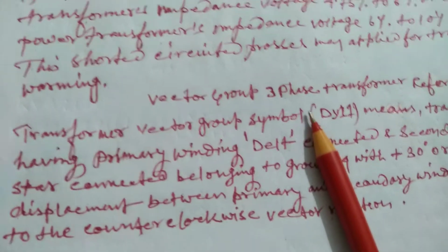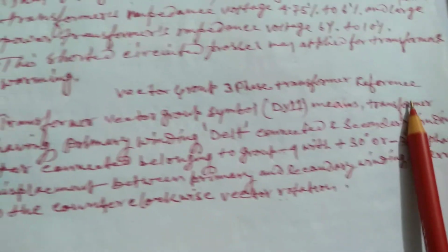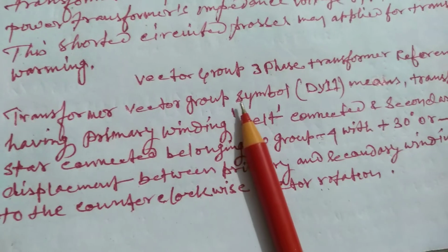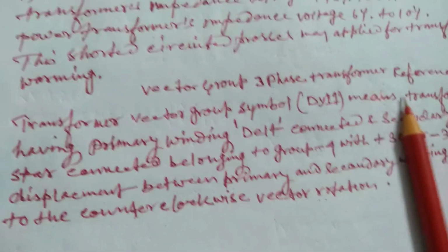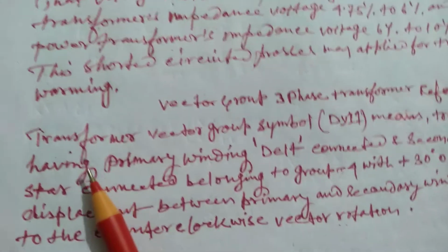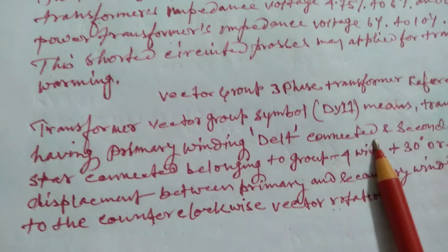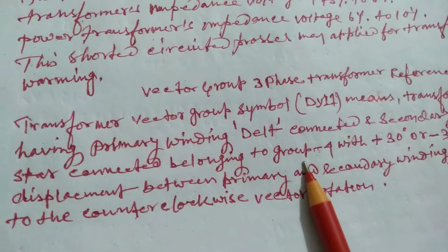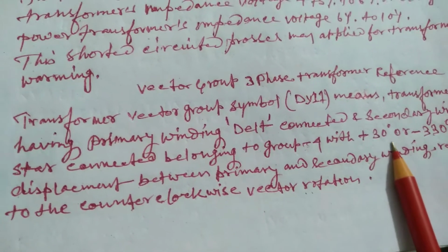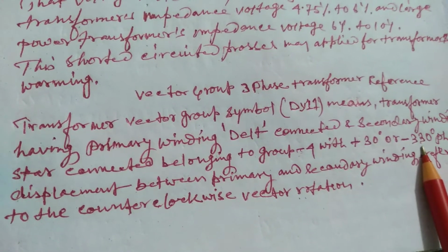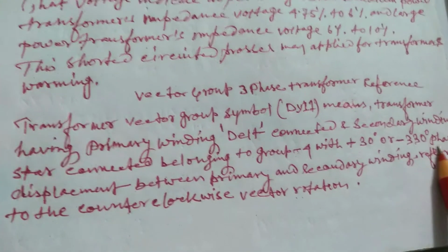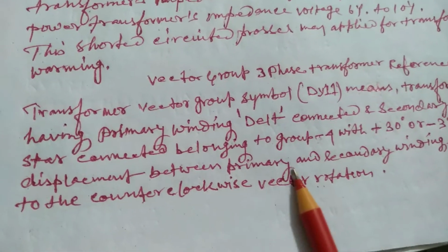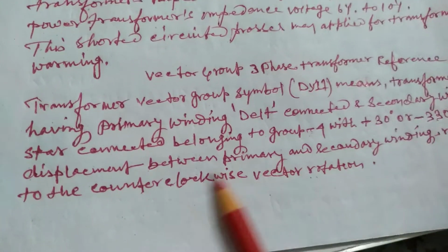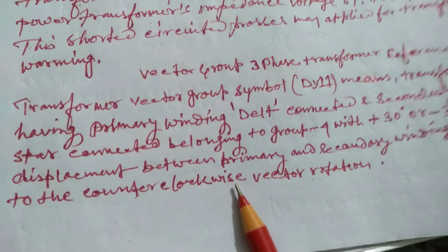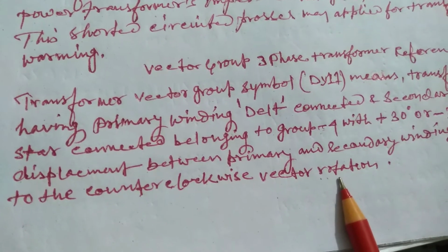Vector group, three-phase transformer reference. The transformer vector group symbol DY11 means the transformer has primary winding delta connected and secondary winding star connected, belonging to group 4, with plus 30 degree or minus 330 degree phase displacement between primary and secondary windings. Refer to the counterclockwise vector rotation.